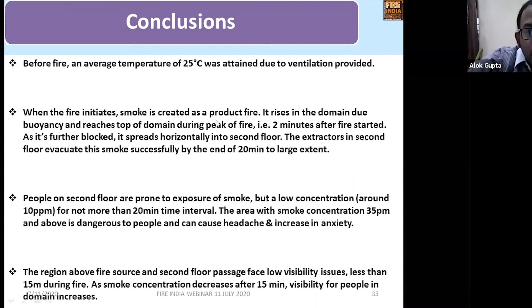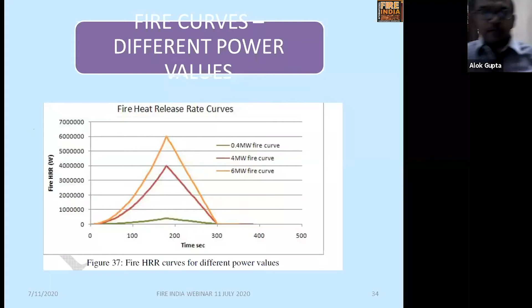Further, we have seen that video, which is a testing of equipment - this is prescriptive based testing, to check whether equipments are functioning or not. We want to know further, like what is the megawatt of fire at which our equipment can fail. This type of analysis satisfies our curiosity, or maybe a fire department person wants to understand what is the maximum fire load that this particular equipment can take up, because every equipment fails - there is a limit to every equipment. So we have further done a study on how much time it will take.